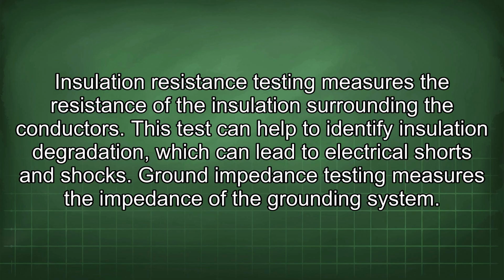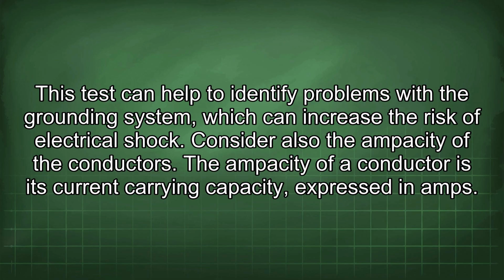Insulation resistance testing measures the resistance of the insulation surrounding the conductors. This test can help to identify insulation degradation, which can lead to electrical shorts and shocks. Ground impedance testing measures the impedance of the grounding system. This test can help to identify problems with the grounding system, which can increase the risk of electrical shock.